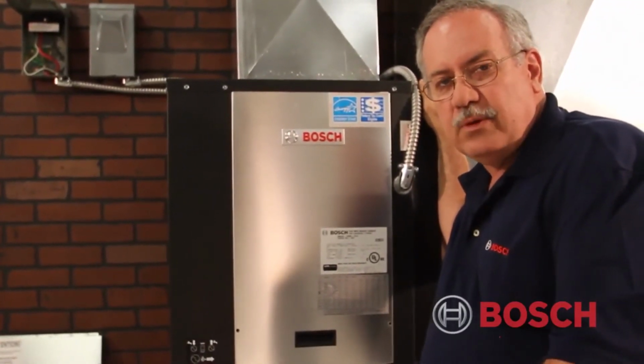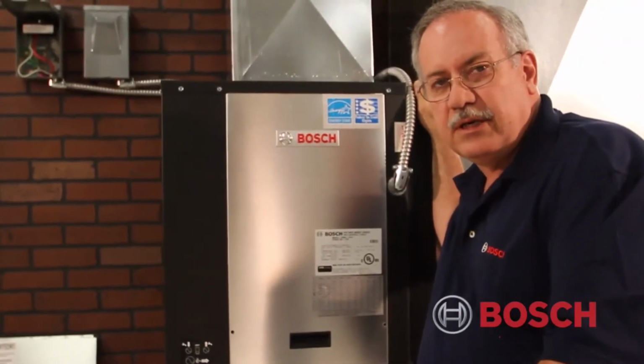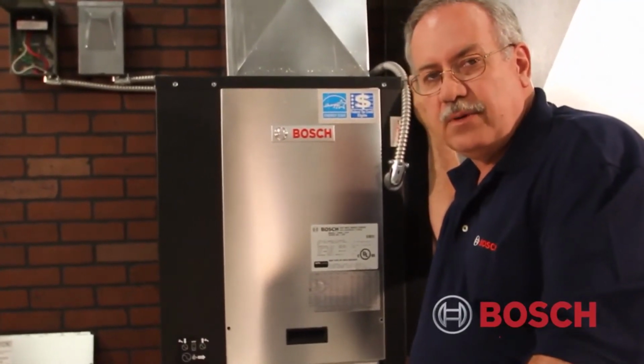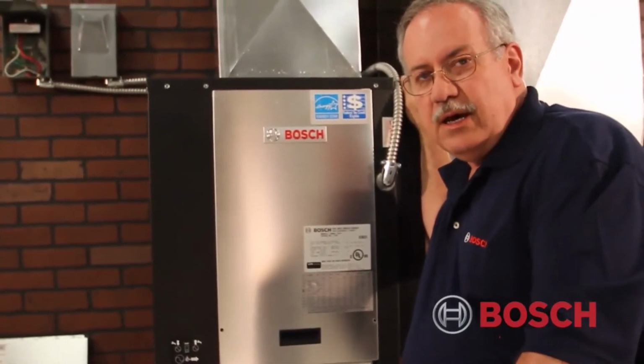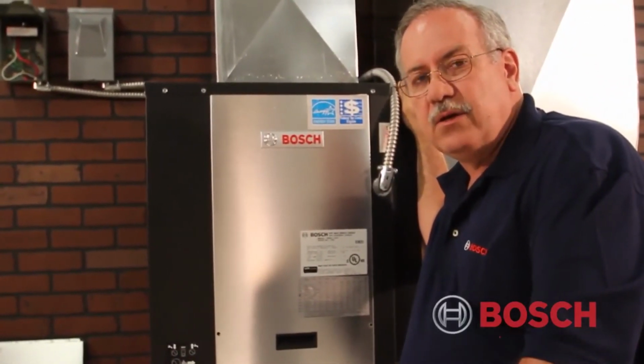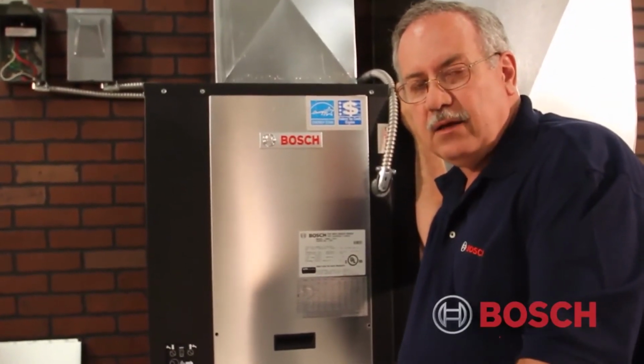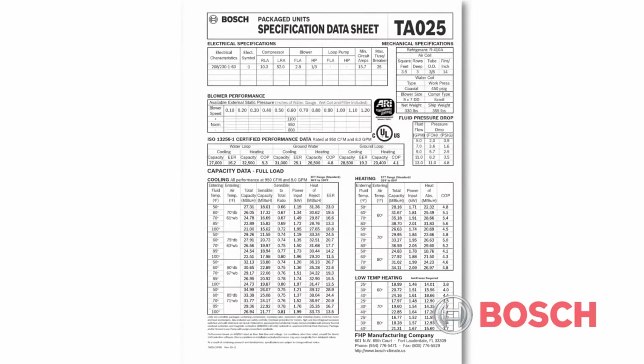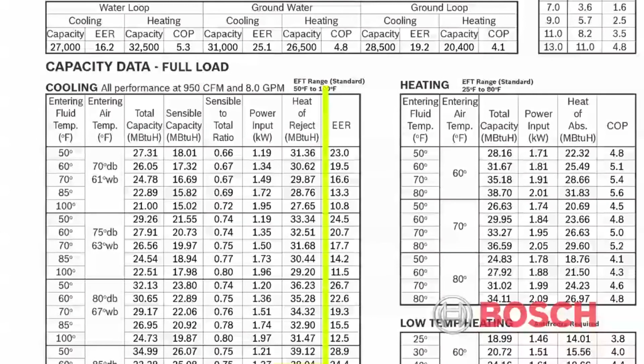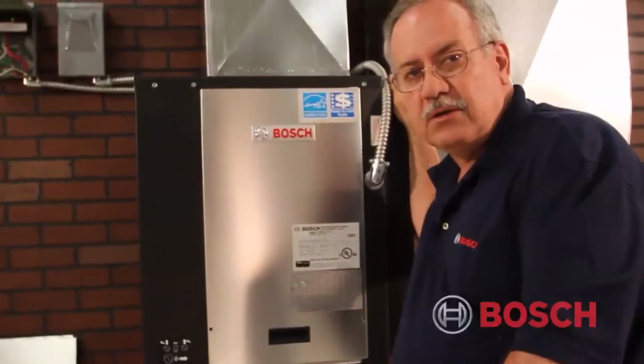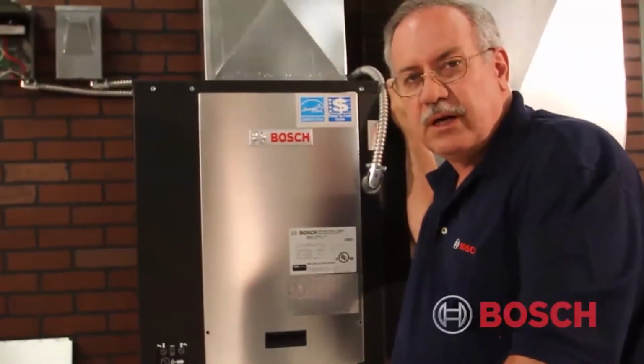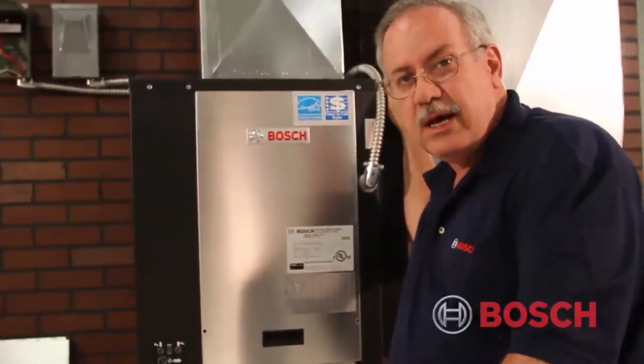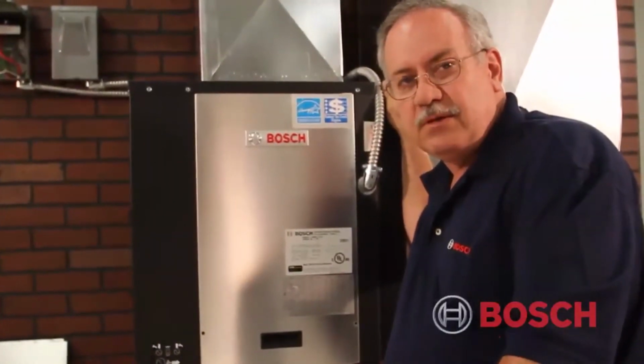So in this particular case, what we'll do is set up all of our components and testing equipment, refer back to the product literature for this particular unit, and then energize it in the cooling cycle. If I'm checking in the cooling cycle, I will be determining what we refer to as heat of rejection. That is the heat that is absorbed from the airflow into the refrigerant, transferred into the fluid. If it is an open loop system, this would be only water. If it is a closed loop system, horizontal or vertical, then the fluid would probably be a combination of antifreeze and water. So we'll have some variables involved with that.